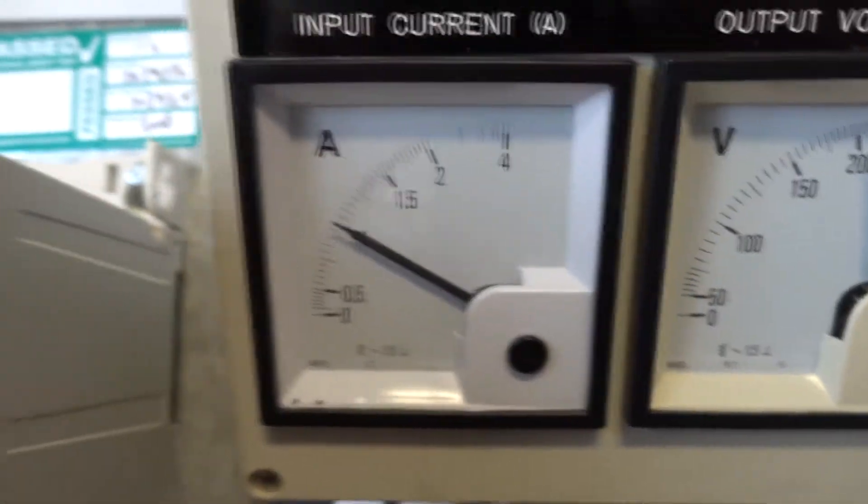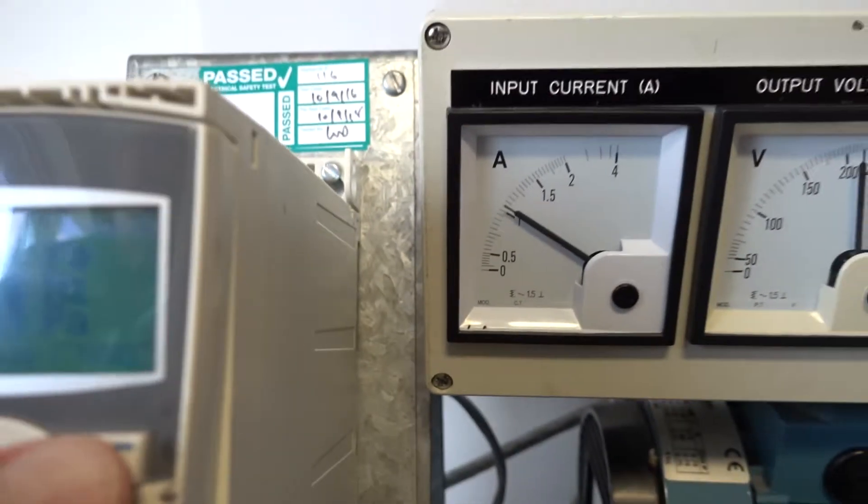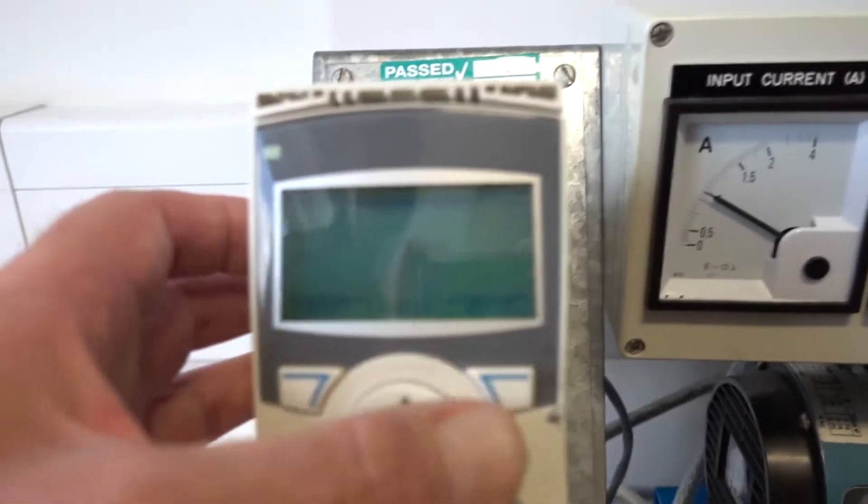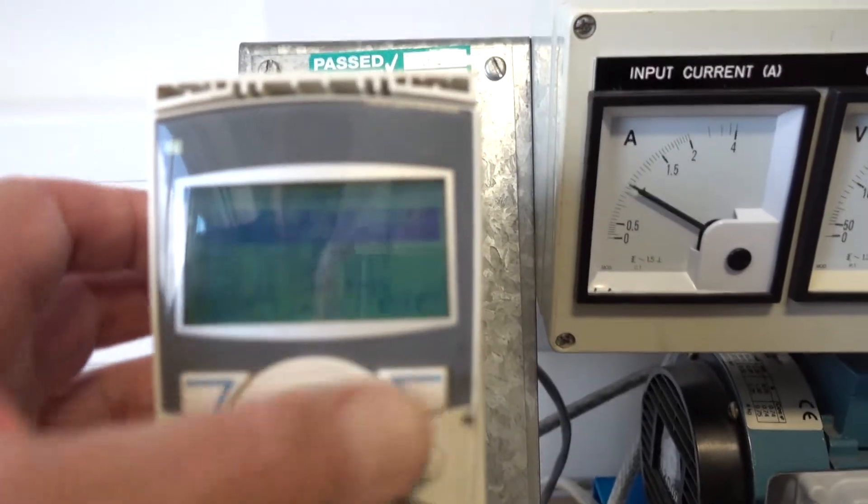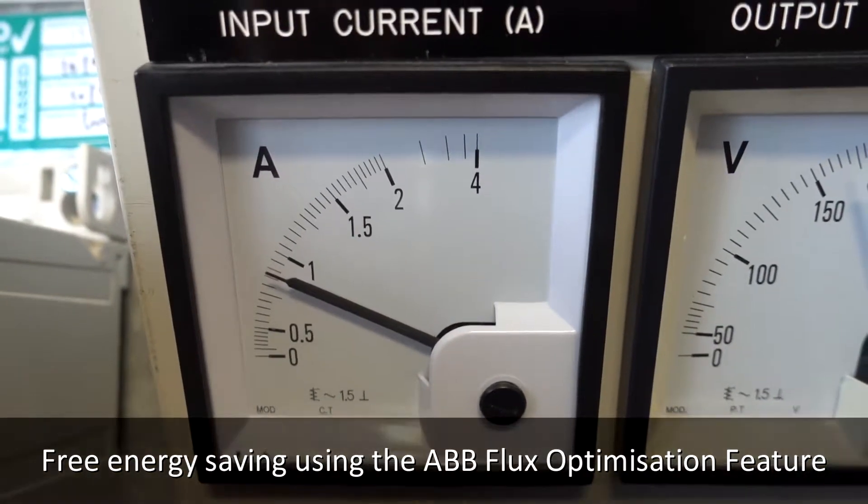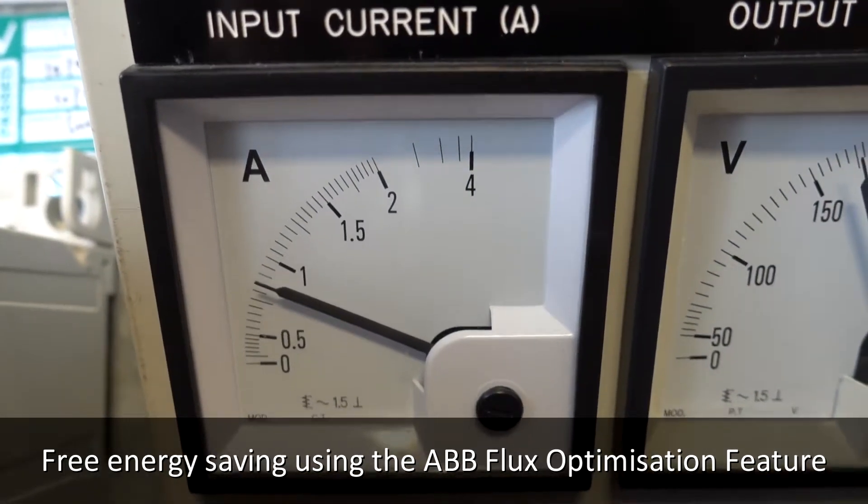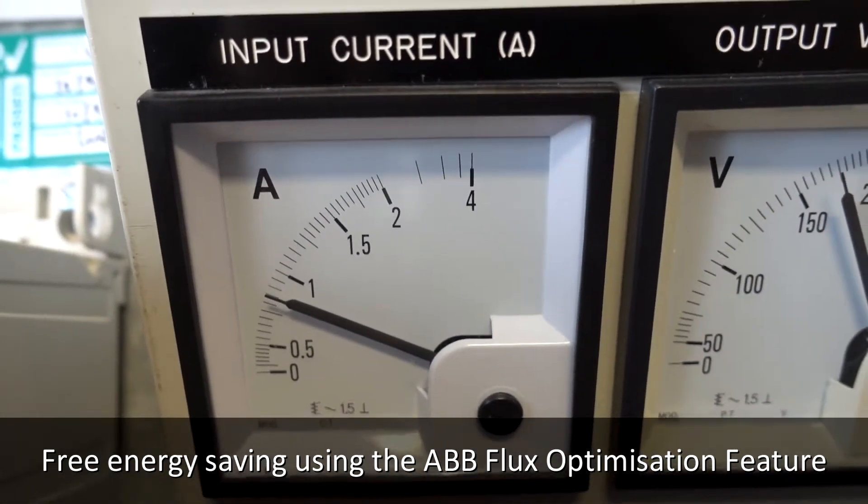As you can see we're taking approximately one amp. I'm switching on the feature now. Please look at the amps. You can see it dropped about 0.8 of an amp. This is free energy saving using flux optimization.